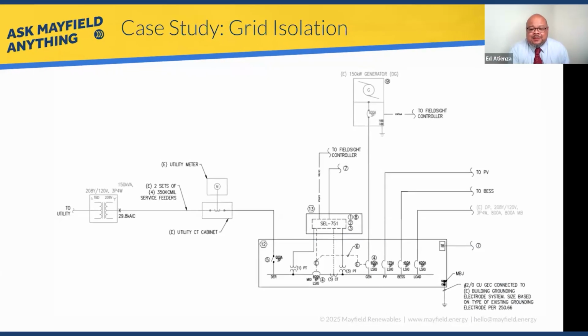I think this is a pretty fascinating drawing. Looking at the 751 and the breaker there at the interconnection, on the left and right side, I see the PTs there, and I don't see any other PTs. So when we're synchronizing, I imagine that connection to the FieldSight controller up top is using the data from the 751 to gather the voltage magnitudes, the phase angles, and the slip frequency across that circuit breaker.